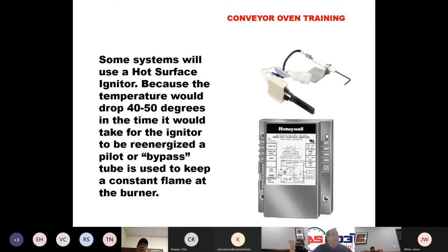If you're ever working on a Lincoln oven and the customer says that it drops 40 or 50 degrees and then it heats back up, get a hot surface igniter. That's going to be your problem.